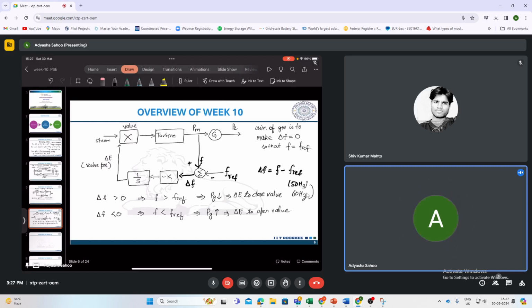So that was your isochronous governor. But what is the problem with this isochronous governor, basically the drawback of the isochronous governor? It will work perfectly fine if we have a single generator. There can be multiple loads, but if we have only one generator supplying all those loads, then the isochronous governor will work fine to maintain the frequency equal to the reference frequency.